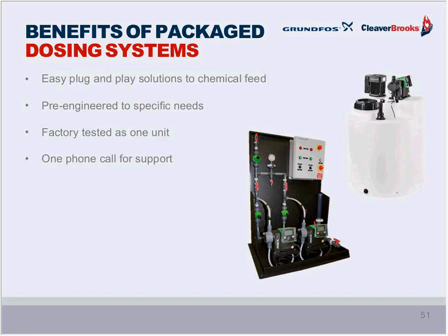But there are package dosing systems that present an easy plug-and-play solution as well and incorporate all the necessary components. Skidded packages have a single source manufacturer, typically providing a single point of contact for support. The alternative to a package dosing system is to piece a system together. This means sourcing components, constructing, and testing all separately from different suppliers. It's more of a larger project. So package dosing systems should be considered, whether skidded or a tank system.